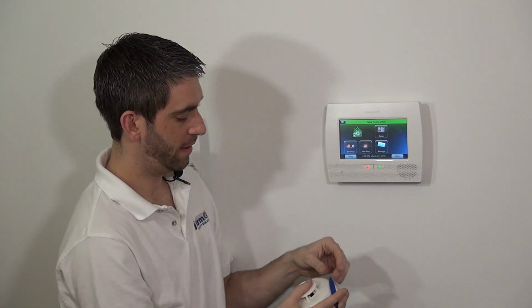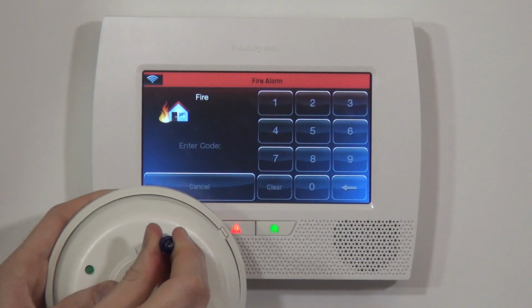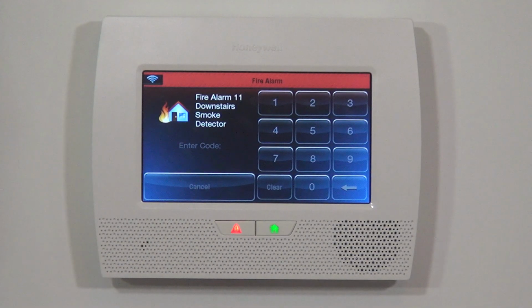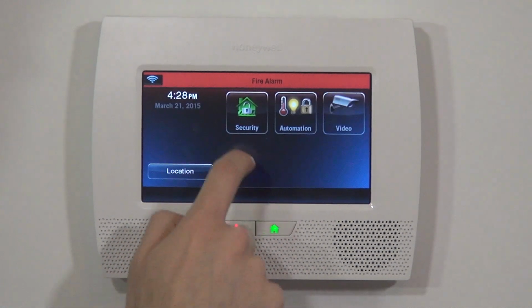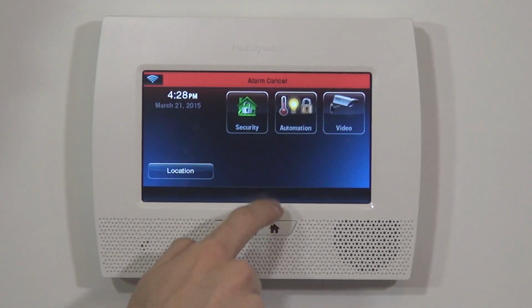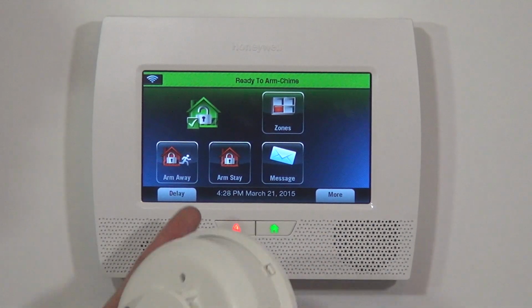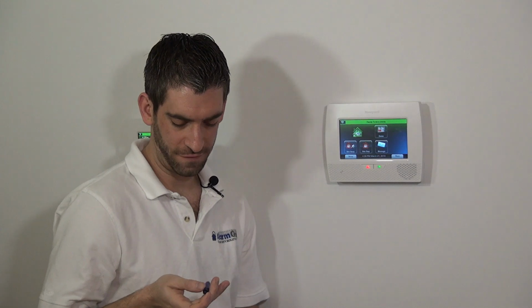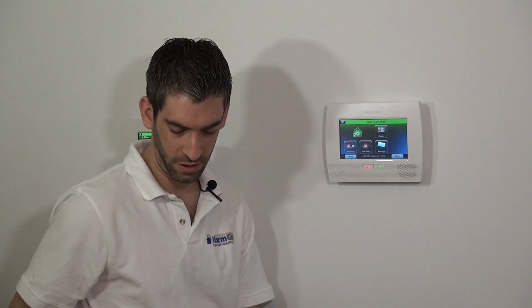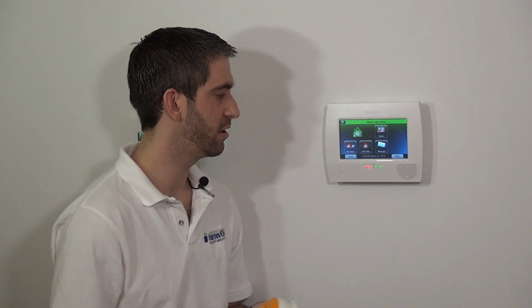So to test, again, we stick it down in. Causes the fire alarm. Disarmed, ready to arm. Cutting it off twice like that with a double disarm clears the alarm away, and we know that our 5808W3 smoke and heat detector was learned in properly.